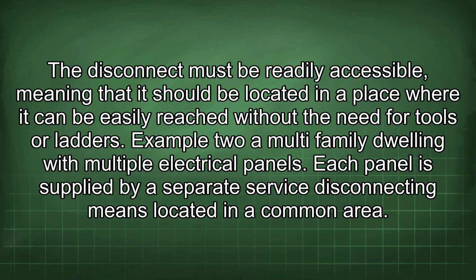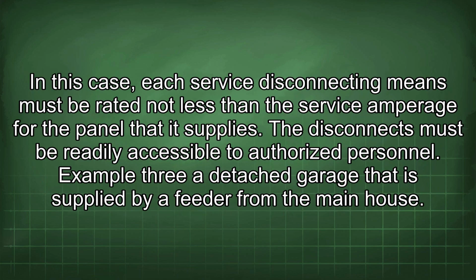Example 2: a multi-family dwelling with multiple electrical panels. Each panel is supplied by a separate service disconnecting means located in a common area. In this case, each service disconnecting means must be rated not less than the service amperage for the panel that it supplies. The disconnects must be readily accessible to authorized personnel.